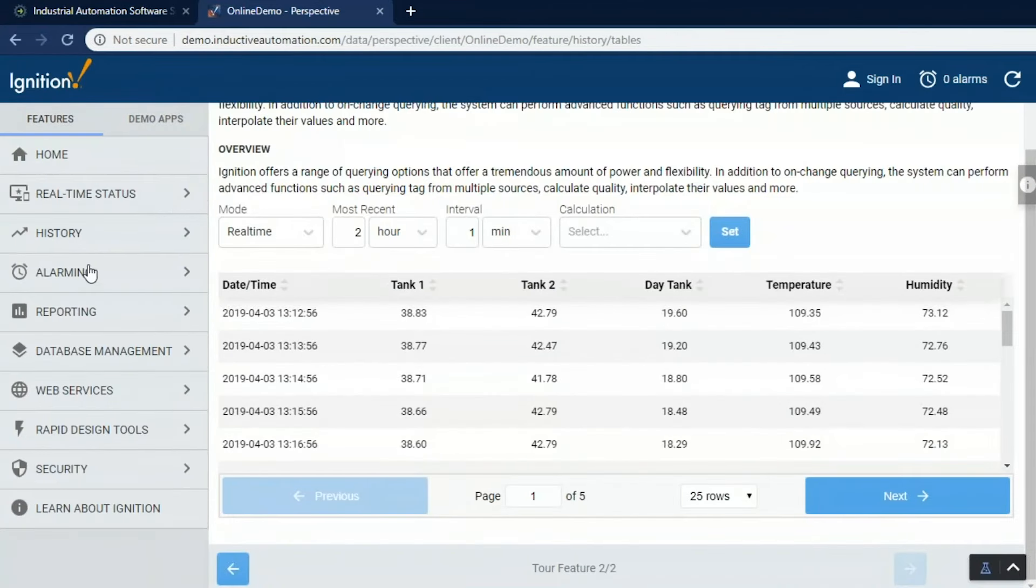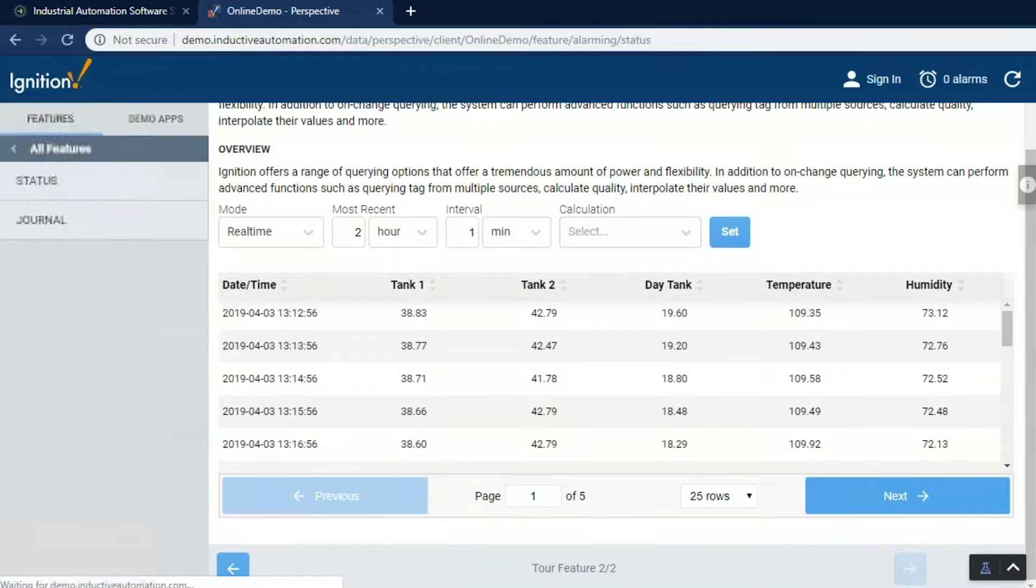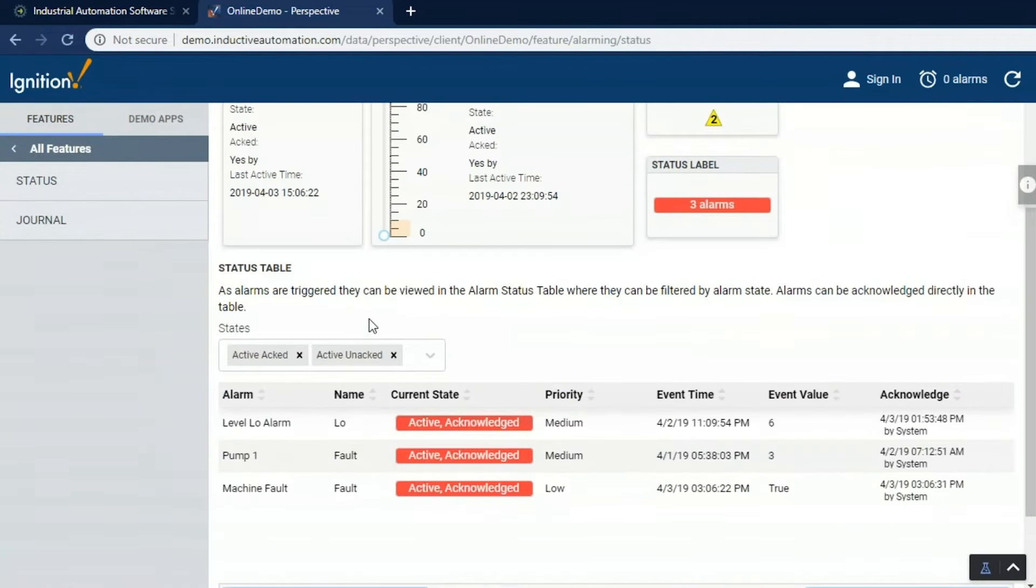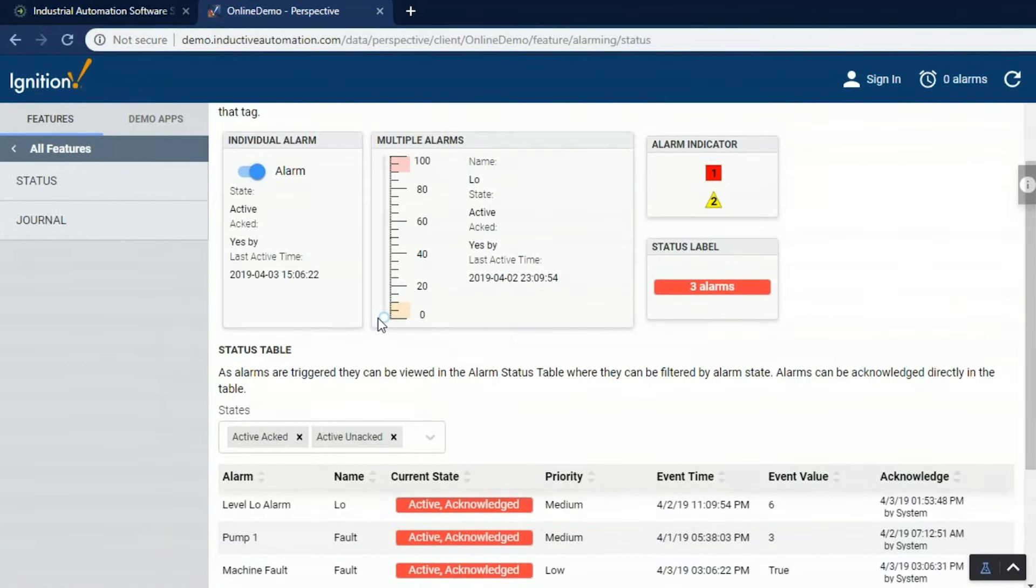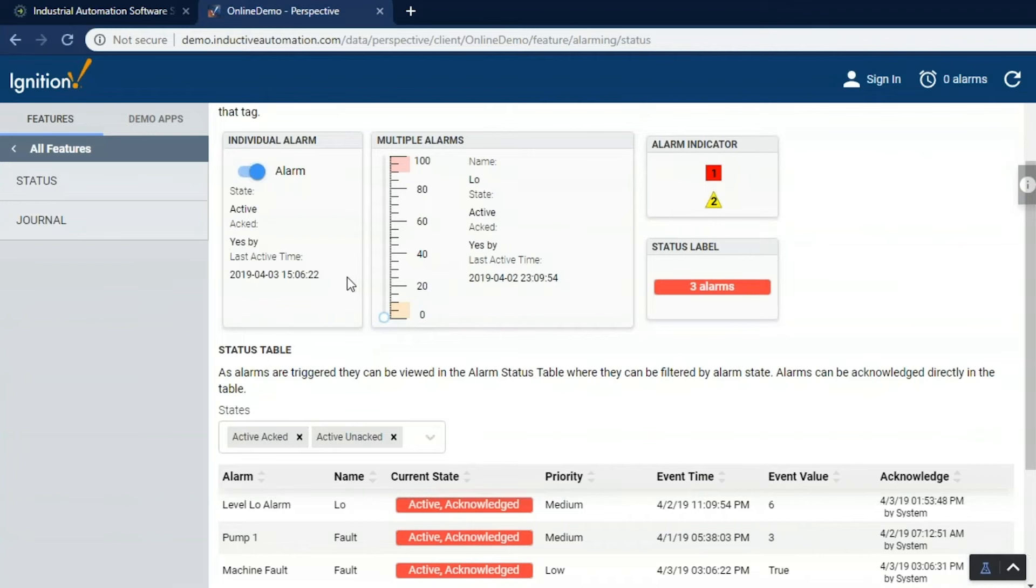We can also take those tags and we can configure alarms on them. So we can see the current status of the alarms. We can log alarms to the database historically. We can notify people through email, SMS, and voice. They're all two-way. We can acknowledge from those sources. So right now, I've got three alarms that are active.